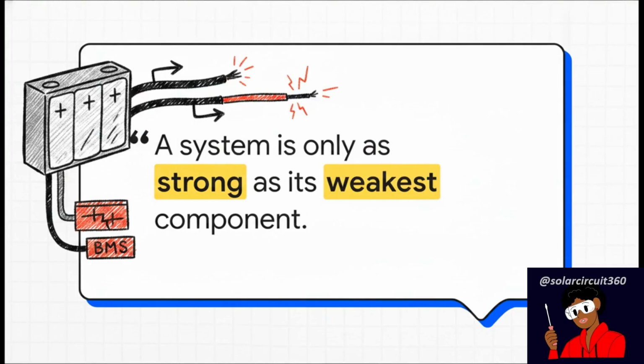So how do we adopt the right engineering mindset and prevent these expensive failures? It really all boils down to this. A system is only as strong as its weakest component. We absolutely have to adopt a current-first engineering mindset. You just have to realize that having the largest, strongest, most expensive battery bank in the entire world simply cannot overcome a single undersized cable, a poorly rated fuse, or a cheap BMS.